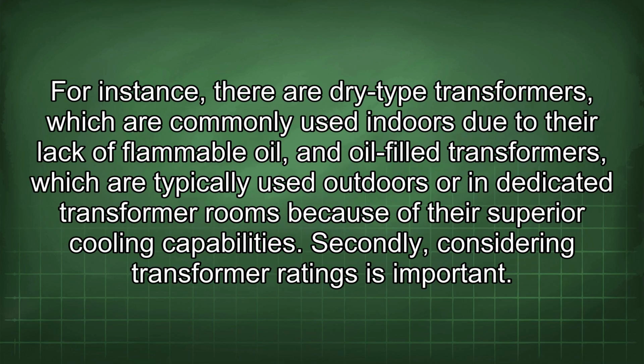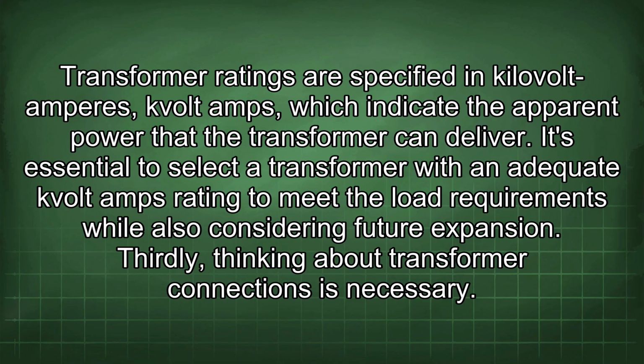For instance, there are dry-type transformers, which are commonly used indoors due to their lack of flammable oil, and oil-filled transformers, which are typically used outdoors or in dedicated transformer rooms because of their superior cooling capabilities. Secondly, considering transformer ratings is important. Transformer ratings are specified in kilovolt amperes, kVA, which indicate the apparent power that the transformer can deliver. It's essential to select a transformer with an adequate kVA rating to meet the load requirements while also considering future expansion. Thirdly, thinking about transformer connections is necessary.